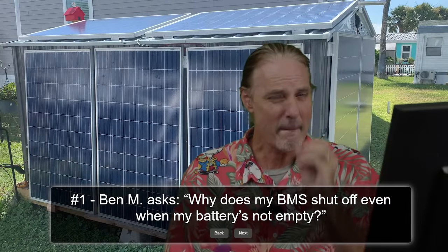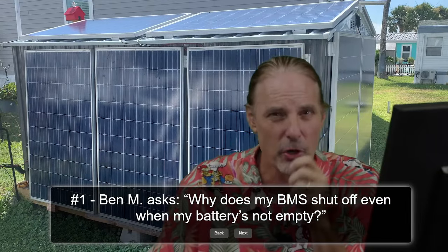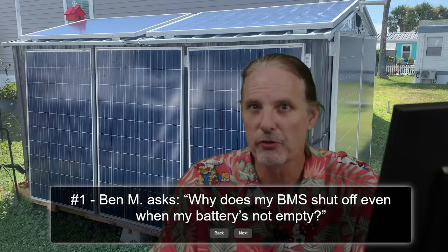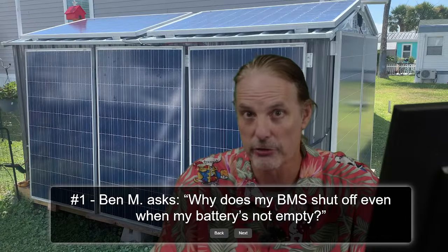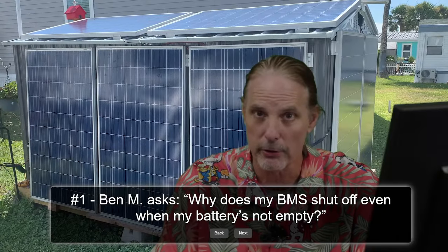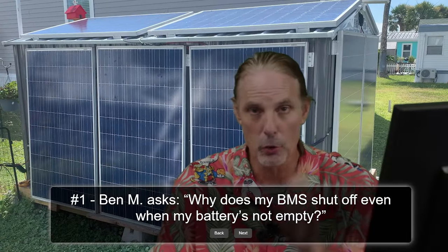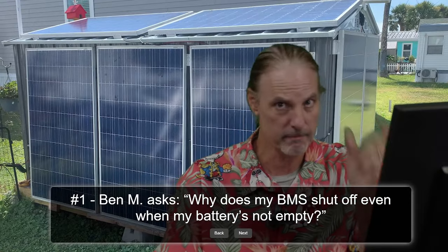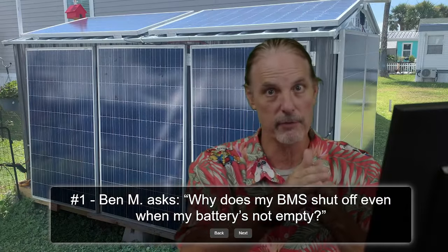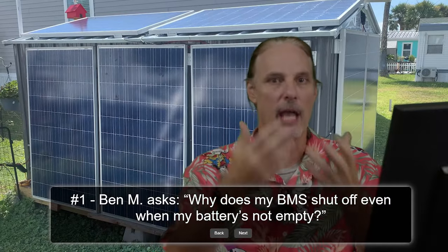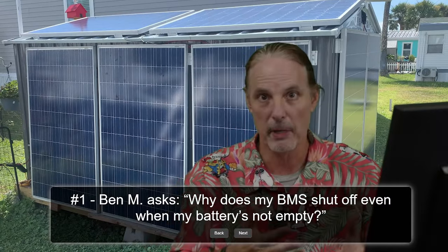Now, some inverters prevent you from ever even seeing the problem. And let's talk about the 6000 XP from EG4 as one of those, where if you're running closed loop, meaning that the inverter is communicating with your battery, and your battery is telling the inverter how much power it can take, how many batteries are connected, how much space it has.